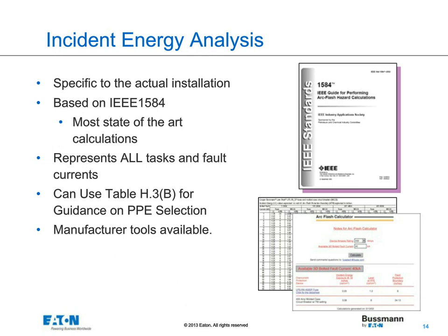I mentioned earlier that you can use Table H3B for guidance on PPE selection. It's not required. And also be aware there are many manufacturer tools that will help you identify the arc flash hazard, based upon given both the fault currents and the type of overcurrent protection used.